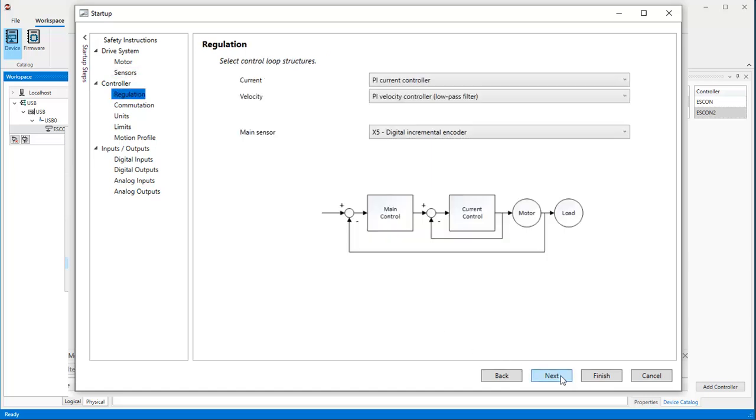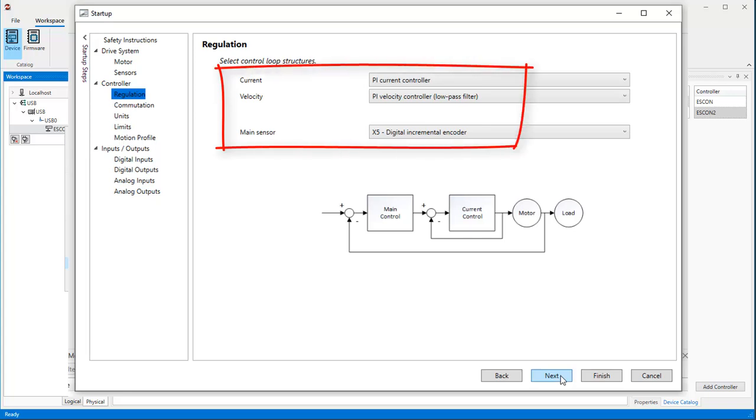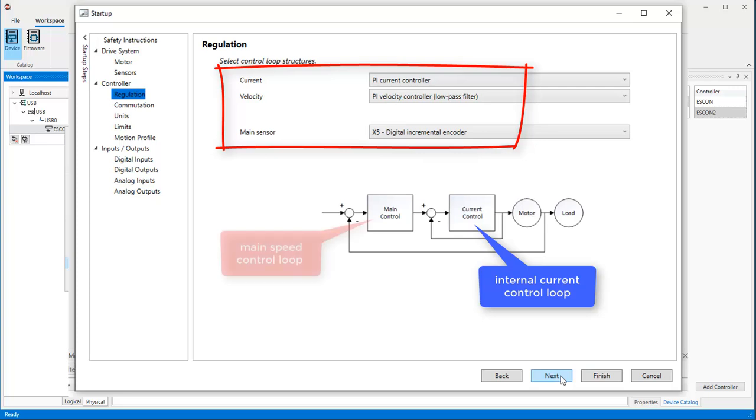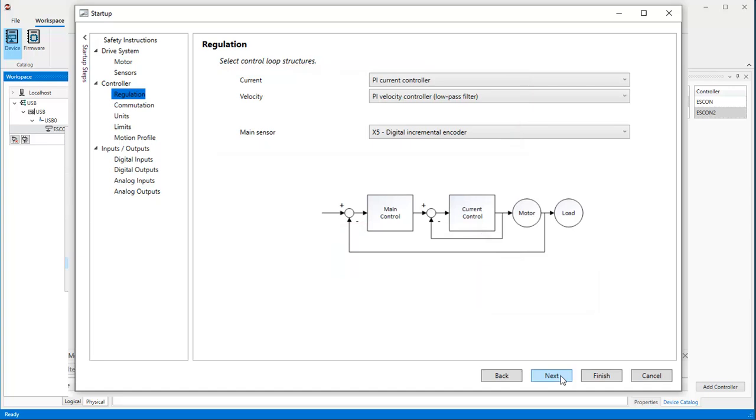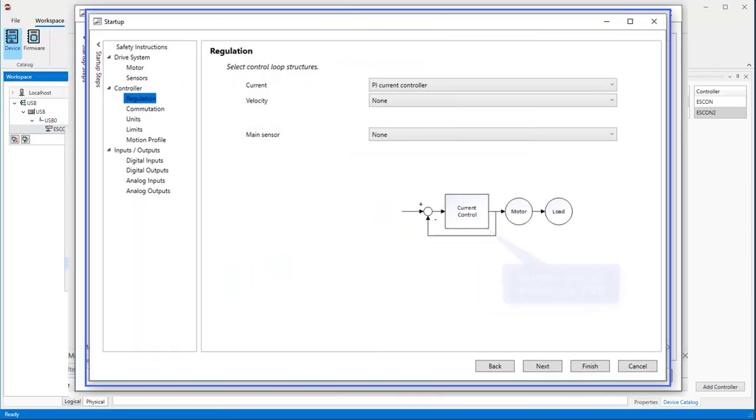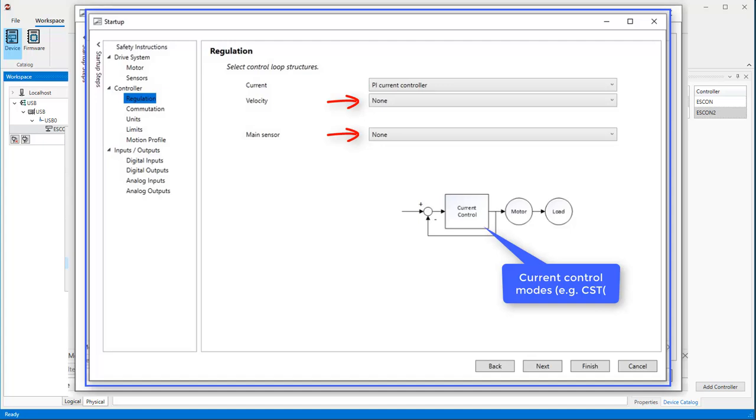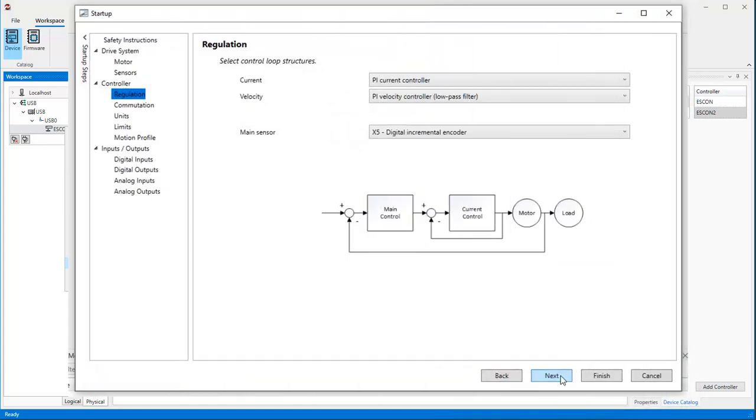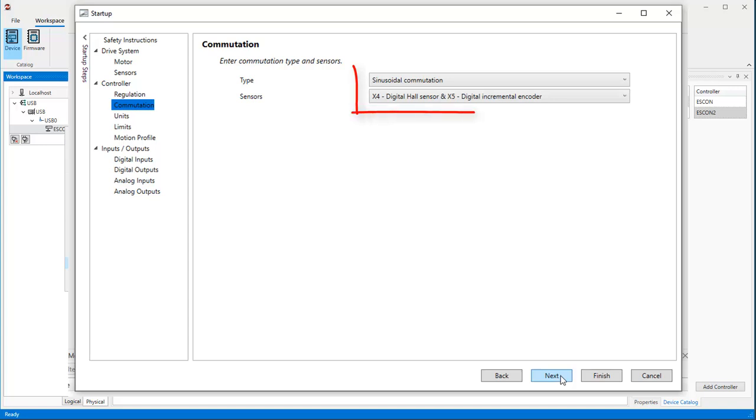We keep the control loop structure. The basic setting shows an internal PI current control loop and an external main speed control loop using encoder feedback. For the CAN open cyclic synchronous torque mode, CST, we would have to set both velocity and main sensor to none. Press Next shows that the commutation is always sinusoidal based on hall sensor and encoder feedback.